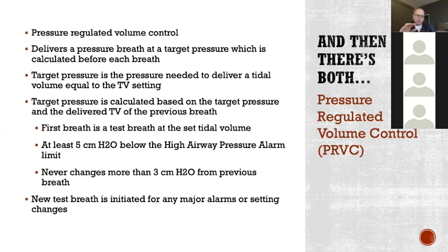But then if it says, oh, that was only 400 cc's, we need more pressure, it's going to increase its pressure. So the next breath, maybe it'll do 25 of pressure and see how much volume it gets. So it's going to do this all automatically in the background. It will adjust up and down as it needs to, and it will adjust the pressure needed. And the benefit, and what this mode really is doing for us, is it's delivering the volume that we want. So we get that kind of guaranteed minute ventilation, so we can really keep their gases in check a little bit better. But we're going to deliver that volume at the lowest possible pressure to help protect those sensitive alveoli. So this is another lung protective mode of ventilation.